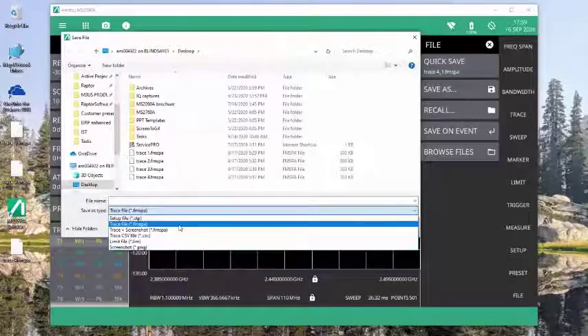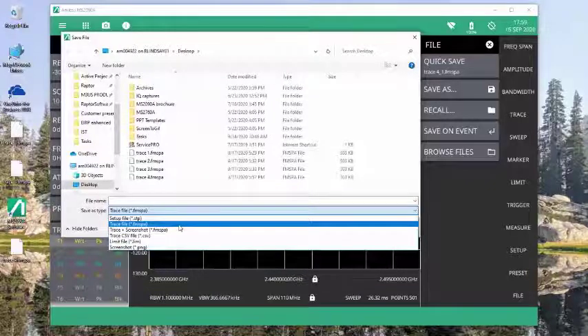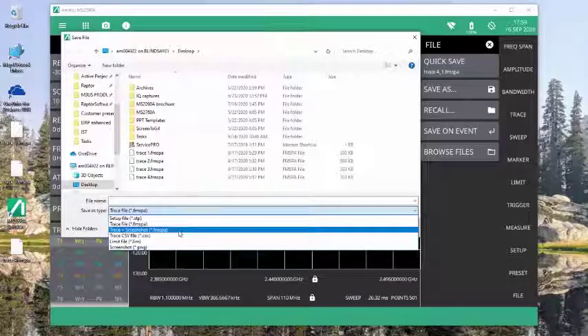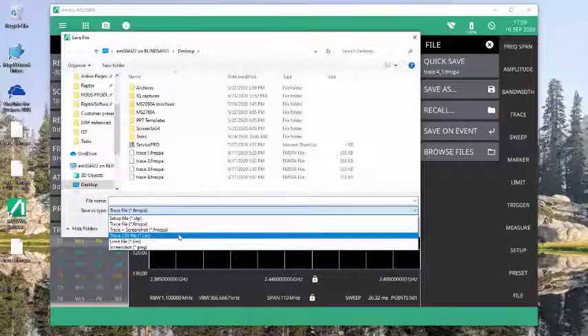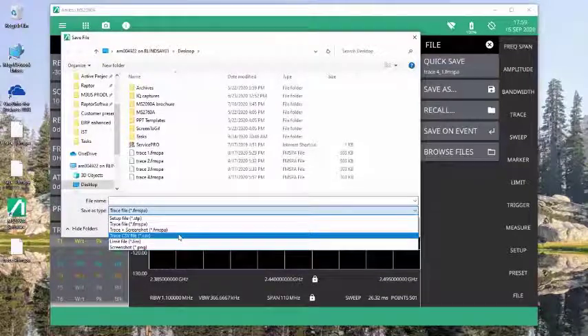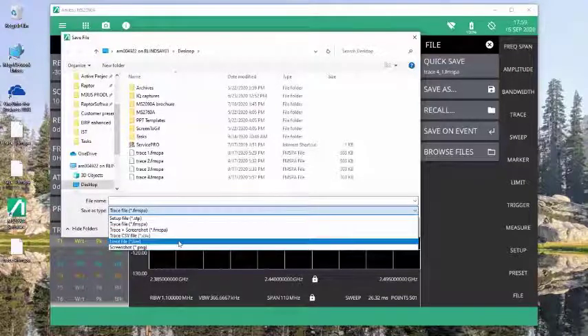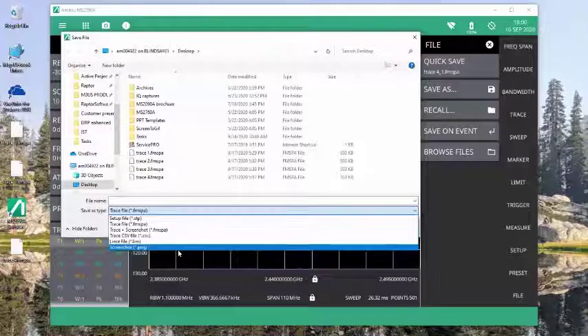To save the trace data and the setup, I do a trace file, which is a .fmspa. I could do a trace plus a screenshot. I could do a CSV file, which will save the trace data into a CSV format. A limit file, which is limits only, or a screenshot.